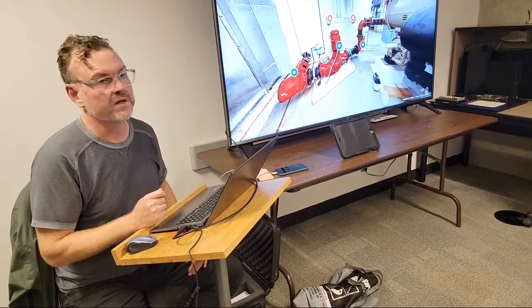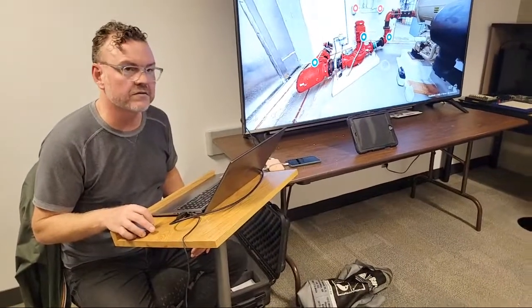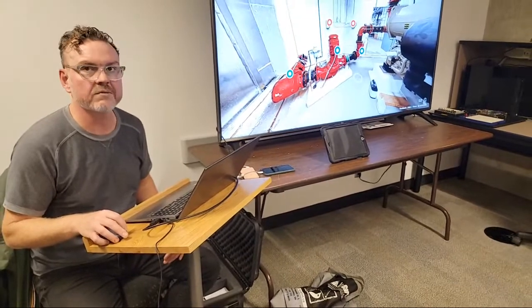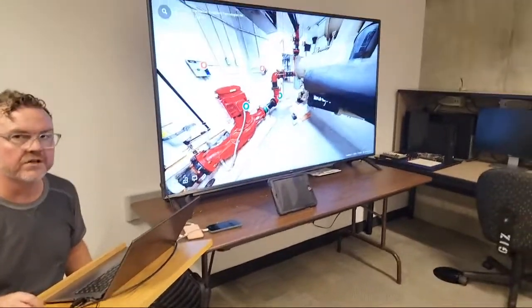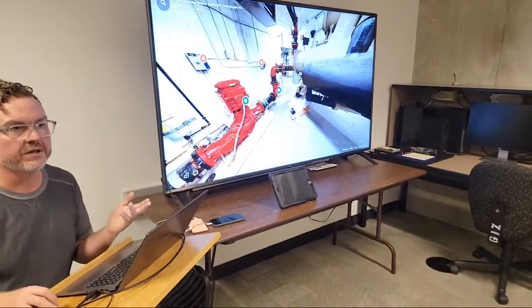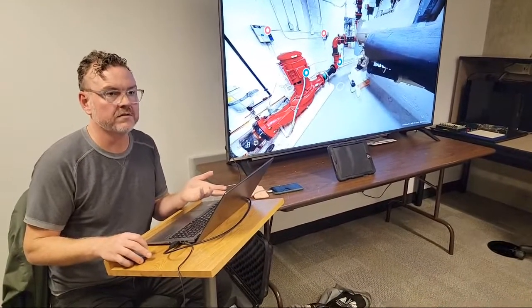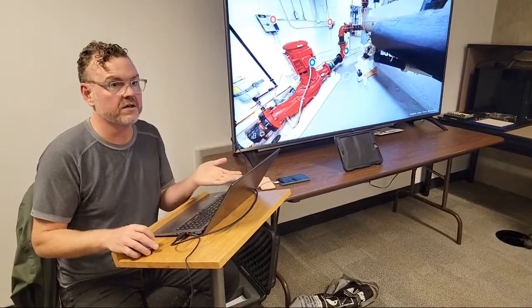Because all I have to do is just go and touch this little valve here, this little needle, just get my wrench on that, and this thing can start running really hot. Once you start understanding the vapor compression cycle, right? So if it is throttled, why was it throttled like that? I don't know. Who did it? Did it happen during commissioning? Oh, I need to see the documents.